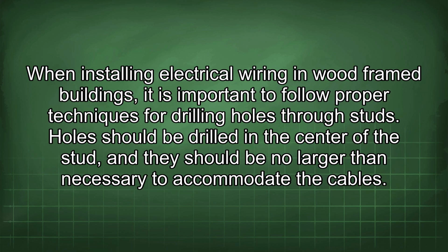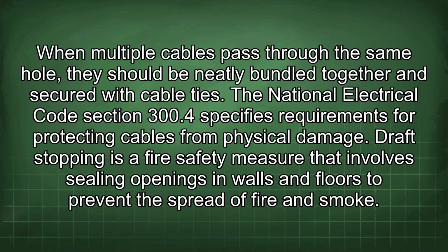800.133. When installing electrical wiring in wood-framed buildings, it is important to follow proper techniques for drilling holes through studs. Holes should be drilled in the center of the stud, and they should be no larger than necessary to accommodate the cables. When multiple cables pass through the same hole, they should be neatly bundled together and secured with cable ties. The National Electrical Code Section 300.4 specifies requirements for protecting cables from physical damage.